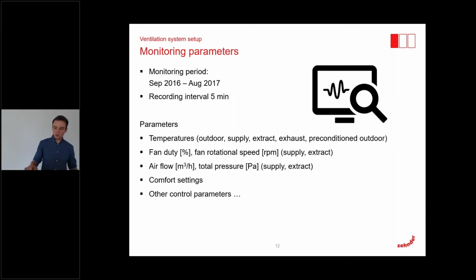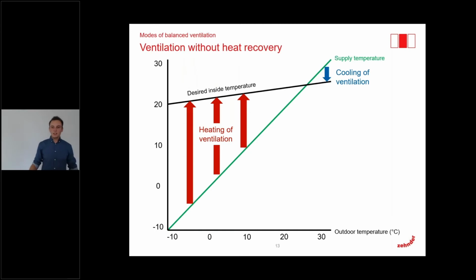So to understand the savings we can reach here, I would like to show you some graphics and point out the potential energy savings. Let us start with a ventilation unit without heat recovery. On the x-axis is the outdoor temperature, and on the vertical axis you have the indoor temperature. The black line shows the desired inside temperature, and the green line shows the supply air temperature.